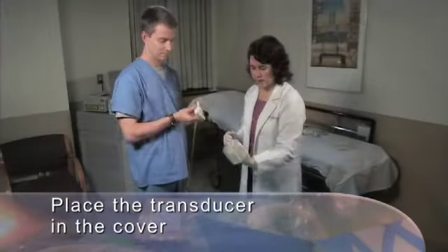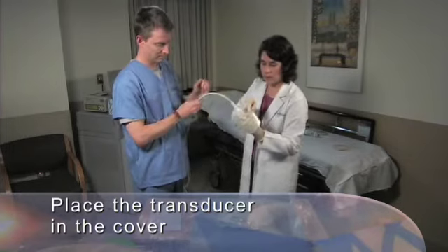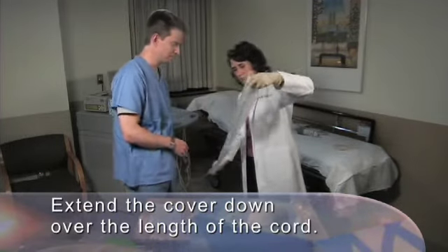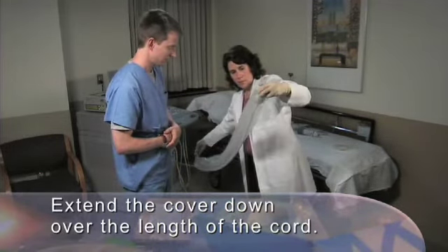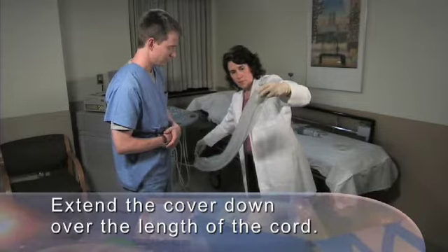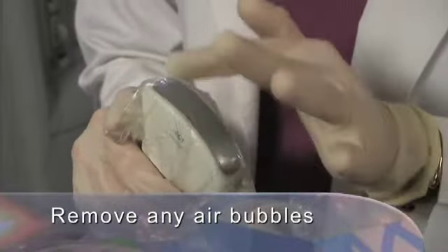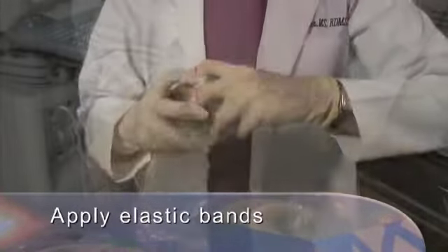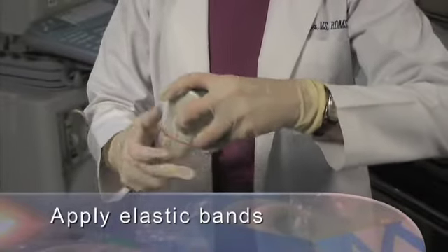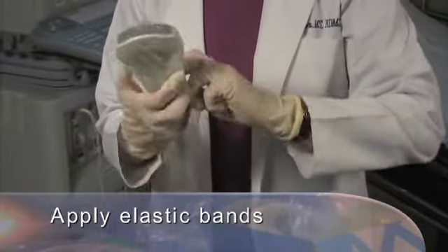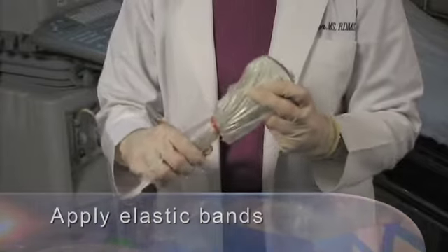The non-sterile person places the transducer into the cover. The sterile person then extends the cover down over the length of the cord, ensuring proper sterile technique. Check carefully and remove any air bubbles that are between the transducer face and the cover. While remaining in the sterile field, apply enclosed sterile elastic bands to secure the cover in place.